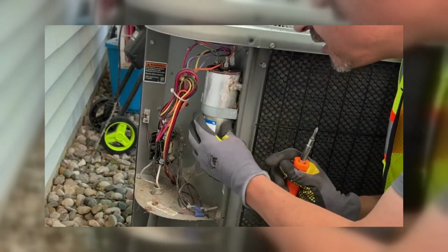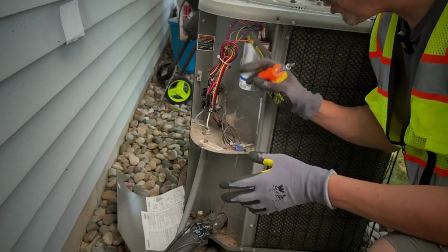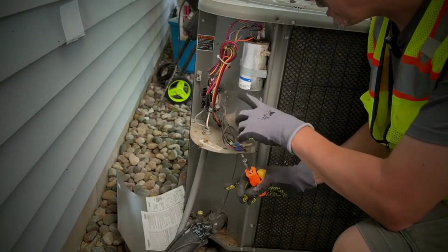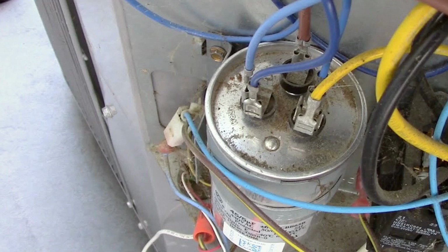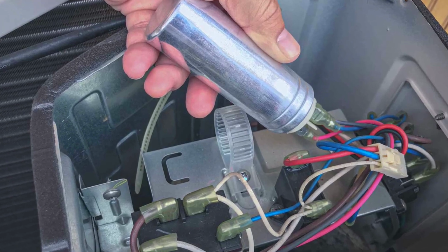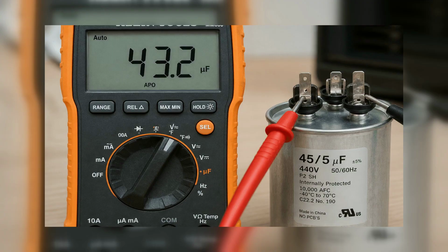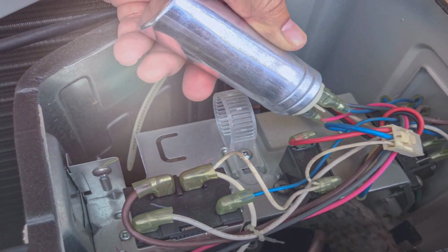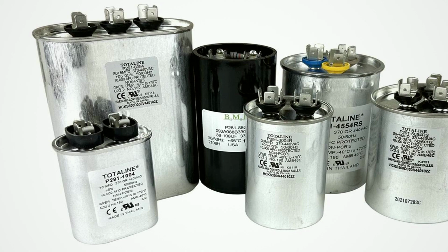The capacitor replacement is powerful precisely because it covers a specific common failure mode. Recognize its limits, and you will never misapply it. One more resource worth knowing. Many HVAC supply houses will test a pulled capacitor for free. Pull the capacitor, drive it to the nearest supply house, and ask them to test it. They have bench testers that give an instant, accurate reading. Bring the old unit in before buying anything, confirm the failure, and buy the correct replacement at the counter for a fraction of what a contractor charges for the same part.